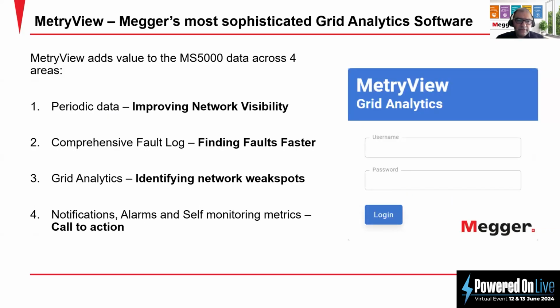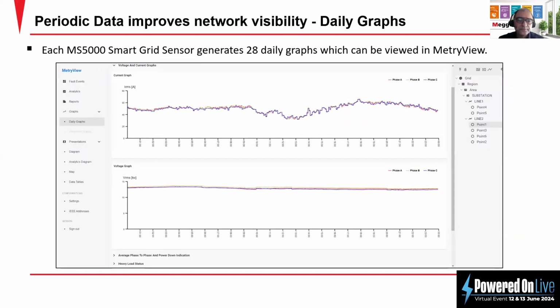MetryView in general adds value to the sensor in four areas, like periodic data, by improving the network visibility. A comprehensive fault log enables the utilities to find the faults faster. Grid analytics, identifying the network weak spots, and having notification, alarm, and self-monitoring metrics. This informs the utility staff to take action and do the necessary things.